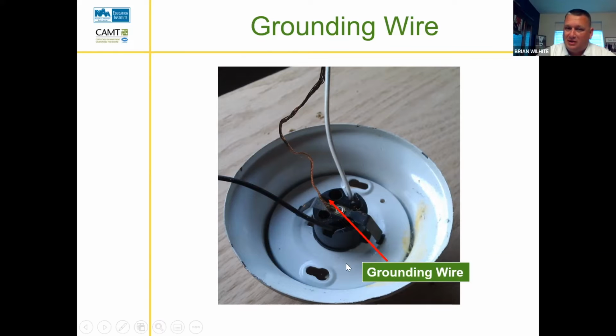We want this appliance to be grounded. So we need to ground. That's why that wire is there, to ground that to the box or ground that back to the circuit panel, so that if this fails, it trips the breaker rather than starting on fire. And so this grounding wire is very important. I've had some service technicians that cut that grounding wire off that condenser fan motor out at the air conditioner or the fan motor in the furnace, and we have to go get another one and put the new one on, because that's not how we do things. All these things need to be grounded. If there's a grounding wire there, it needs to be used.